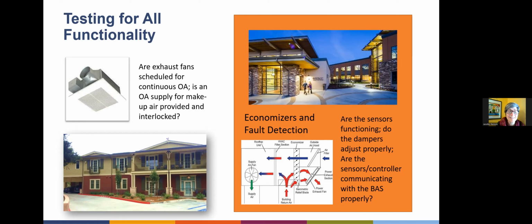And so we did end up having to go back to the engineers and the design team and say, okay, these things have to be interconnected. What's the solution? And there was a viable solution where we were able to utilize a knockout in the heating and cooling system for each of these spaces that provided the balanced outside air with the damper. So it worked out, but catching that before occupancy, before the construction was finished, was a huge win for the owner. It could have been worse.